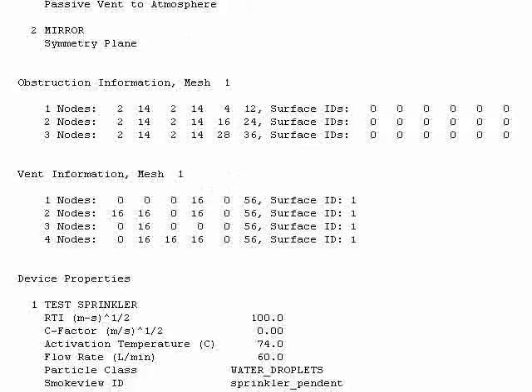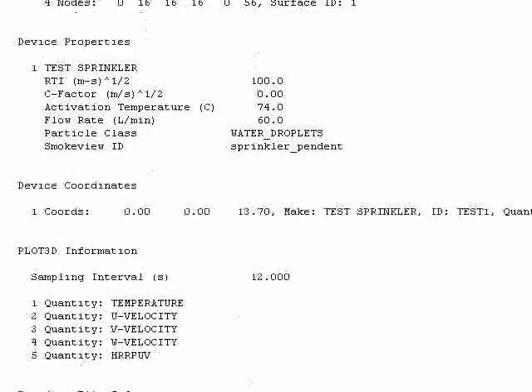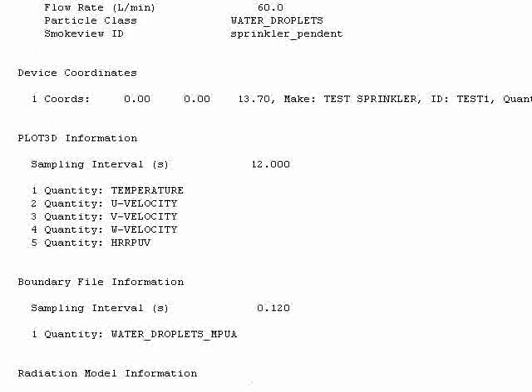It will tell you surface conditions, device properties. You see here this was a sprinkler that you ran. The model had an RTI of 100 and it had an activation temperature of 74 degrees Celsius. And the flow rate was 60 liters per minute.